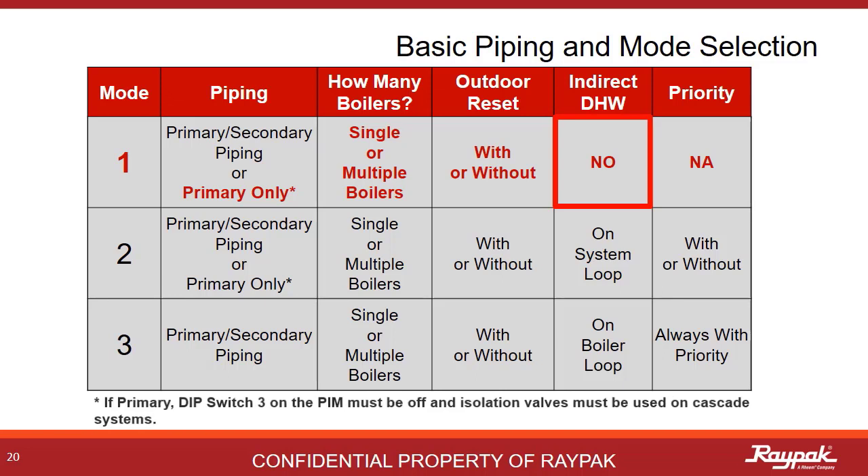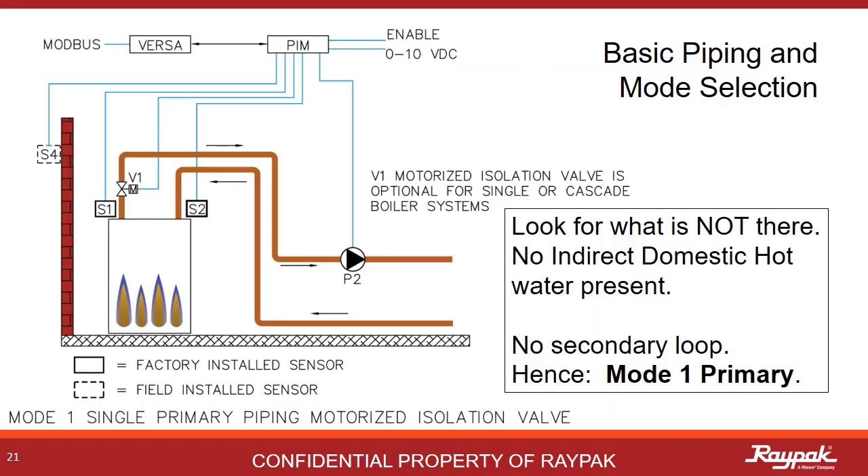Always turn off dip switch number 3 on the PIM for Versa primary systems — this tells the boiler it is plumbed primary only. This is a mode 1 primary plumbed system with a single boiler. As you can see, there is only one loop in a primary system. In some geographies, a motorized isolation valve is required even on single boiler systems, and it should be set to spring to open, power to close.